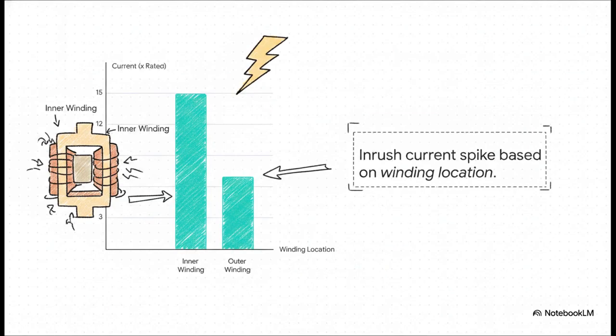Now, what's really interesting about this inrush current multiplier is a design secret hiding inside that geometry. When you first energize a transformer, the core briefly saturates and it pulls a huge spike of power called inrush current. But here's the crazy part. The physical placement of the windings completely dictates the size of that spike. Usually, the low voltage winding is placed on the inside, right up against the core. The high voltage winding is then wrapped around the outside.